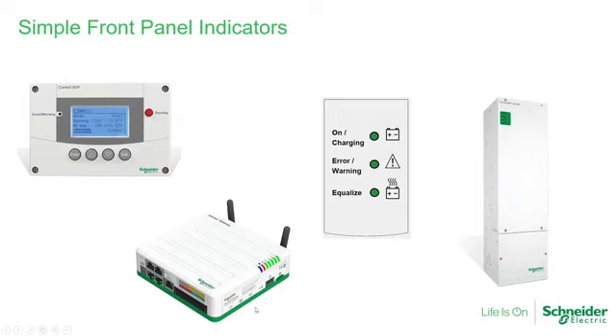The system, because it is in the Xanbus network, the MPPT80 can be programmed with the system control panel, which will be part of the network. Here you program inverters, charge controllers, or you may have a gateway in the system. And the gateway will actually allow you to program all of the devices, either locally while you are at the site, but also allow you to access them via the cloud. And you can actually program the settings using the cloud remotely, locally using the gateway.